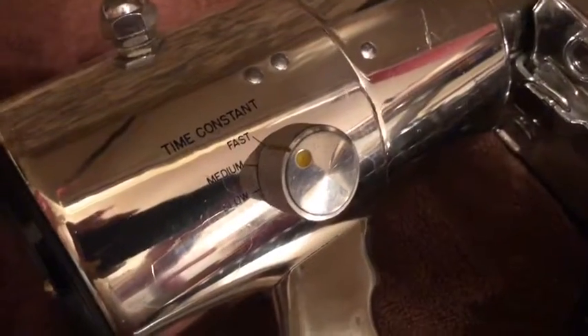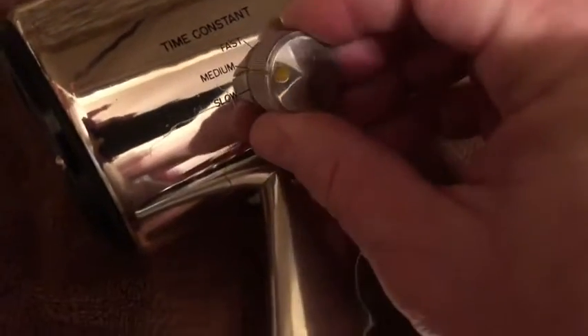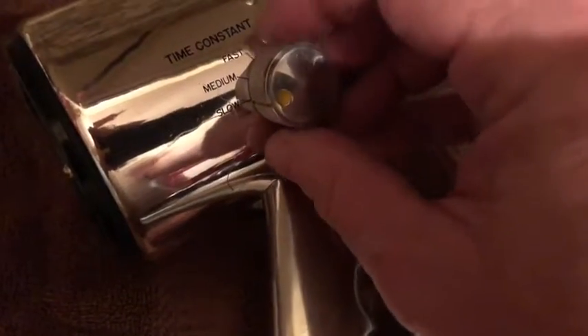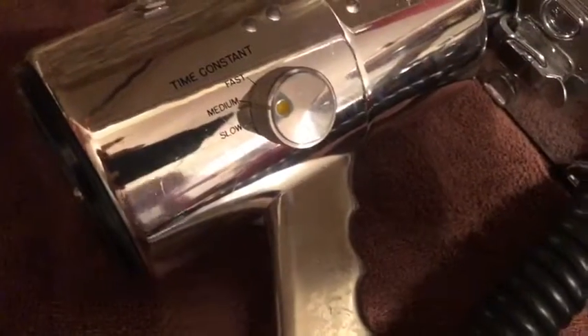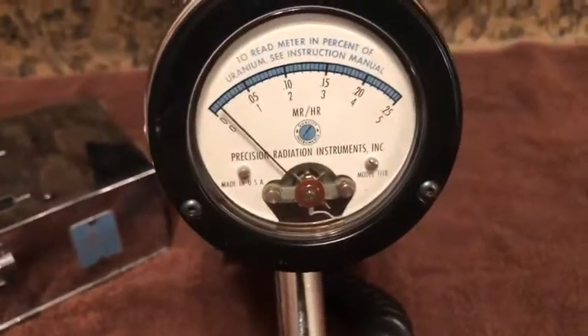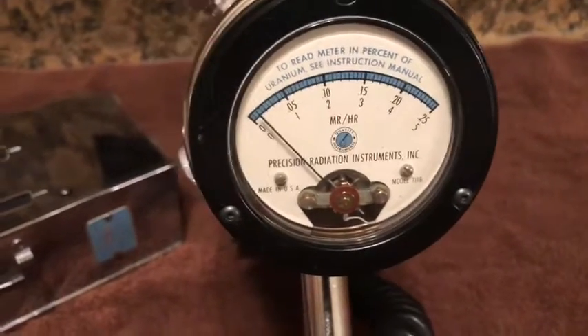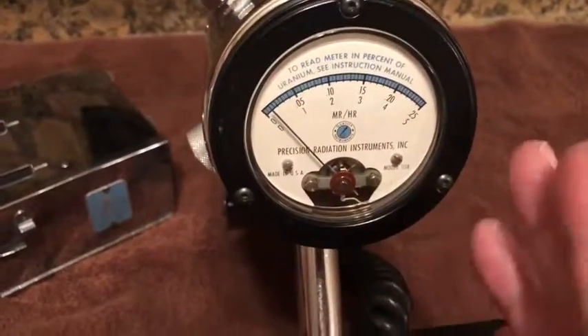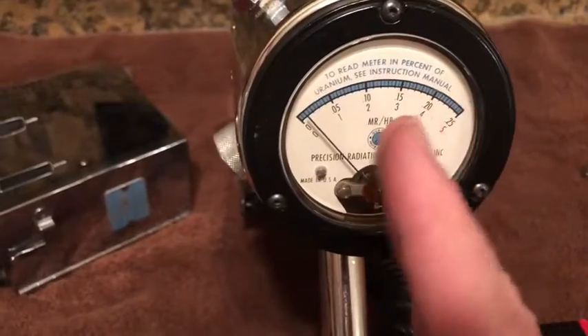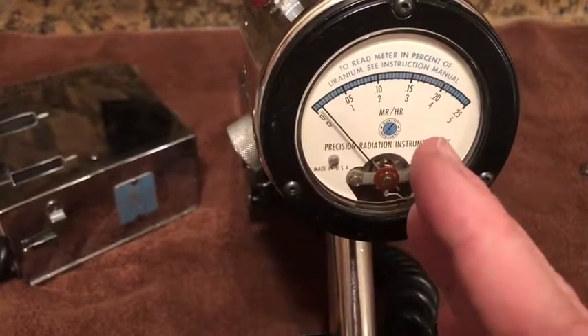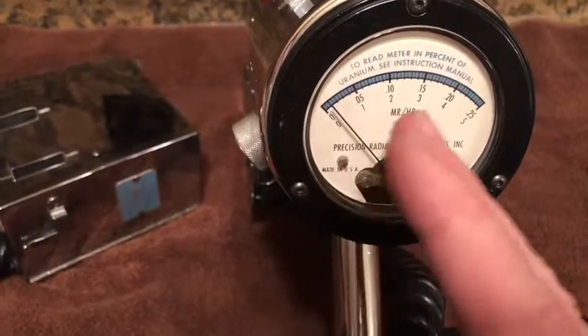On the right side of these units, they have the time constant switch. They've got fast, medium, and slow. The best one to have it on is medium. Basically, what this does is steady your meter, because if you have it on fast, the meter fluctuates wildly, all back and forth. Medium slows it down. And if you have it on slow, it's really, really slow.